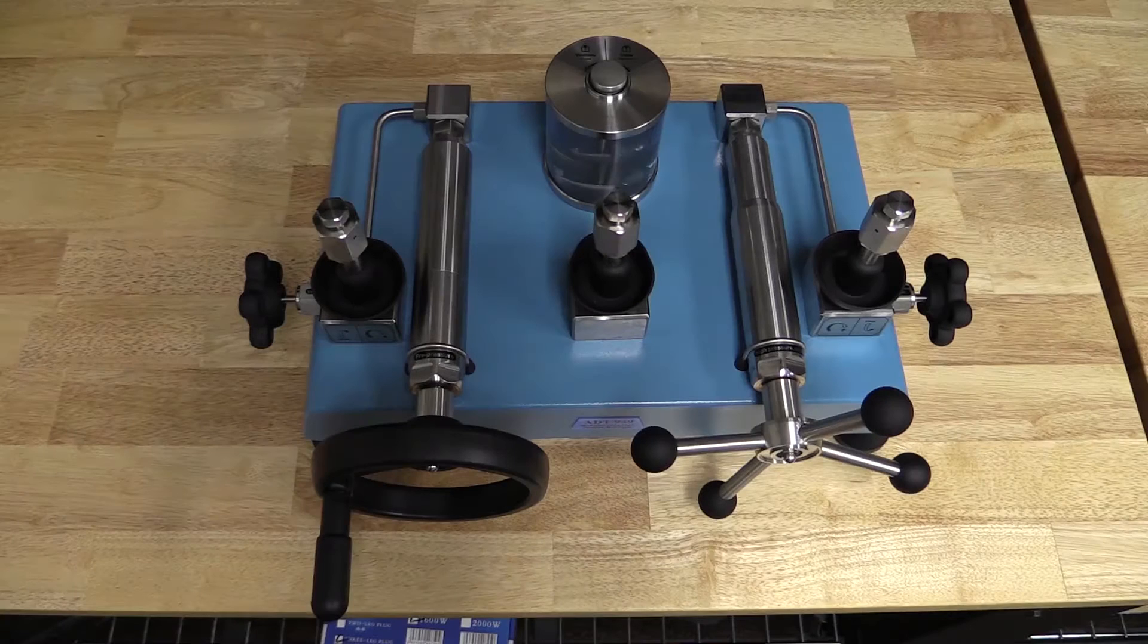The Additel 936, 938, and 949 use a dual screw press system. The screw press on the left is a high volume pre-pressure piston. This side is used to pre-pressure the pump to obtain some higher pressures.